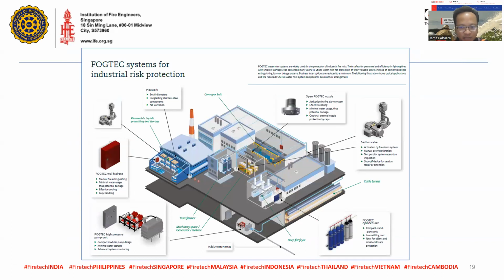Now, for industrial risk application, it's the same thing for a certain power plant. You have your control room, your switchgear room, your transformer, maybe your cable tunnel. Instead of having those multiple systems, for the transformer maybe you use a foam system or a deluge system. In your genset room, you're going to use a CO2 system, that is a gas system, or in your office, you're going to have a sprinkler system. But for water mist, everything will just be a water mist system with a centralized pump.